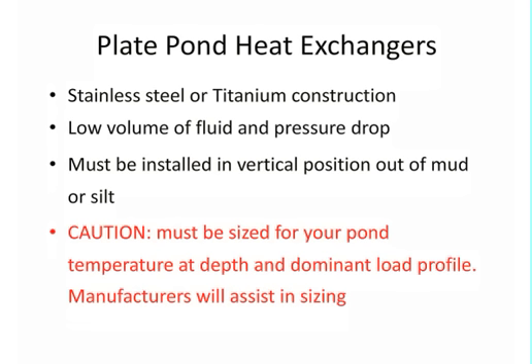I've actually done both. Some of the advantages, well, they typically have low fluid volume. They're typically 3/8 inch thick between the walls, and they don't have much pressure drop for fluid flow. Some things you need to be aware of, folks. Must be installed in a vertical position and up and out of the mud and silt. For those of you that live in a heating dominant climate, I want to make sure you are very well informed. You must size that particular plate heat exchanger for the temperature of your pond water and your dominant load profile. Please make sure you contact the manufacturer of your choice for these plate heat exchangers and work with them to make sure you have the appropriate size for your area.